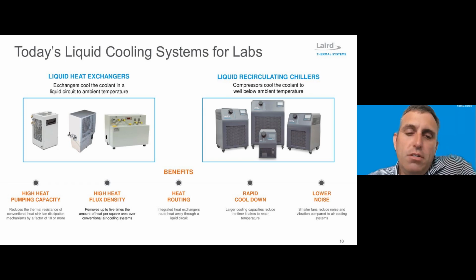So there's a number of benefits that these liquid cooling systems provide within the analytical space. One is high heat pumping capacity. When we think about the actual part that's being cooled, we're passing a liquid through some type of channel, whether it be a cold plate or a simple tube that's immersed in liquid. This has a much higher heat capacity than that of air. So when we think of a fin heat sink mounted on a component that's blowing air over this, there's also an ability to remove heat from very high heat flux density applications. So electronics are a big one here. This has to do with the high thermal conductivity of the liquids, the heat capacity, as well as the amount of mass flow that we can send through one of these components when you think of it relative to air.